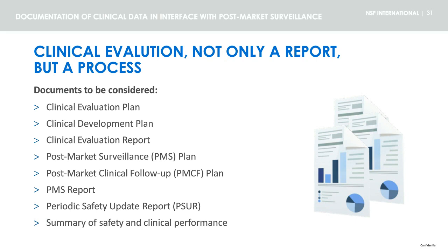However, the preparation of a clinical evaluation report involves a continuous process to acquire and evaluate clinical data. This data should then be documented not only in the clinical evaluation report, but also in a number of other documents, the requirements and update of which differ according to the medical device classes. In the next slides, we will go through the requirements for the preparation of these documents.